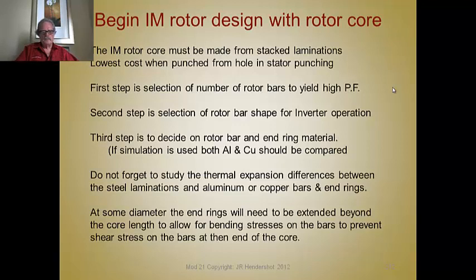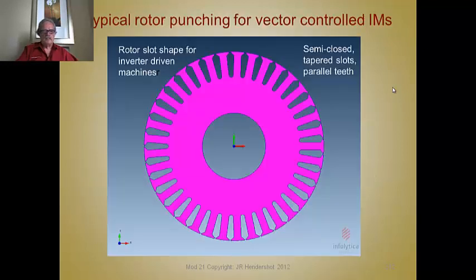At some diameter the end rings will need to be extended beyond the core to allow for bending stresses on the copper bars and to prevent shear stresses on the bars. Otherwise, if there are shear stresses, they're going to fatigue and fail. I've noticed that some large machines — grid motors — have their rating determined by the number of starts.